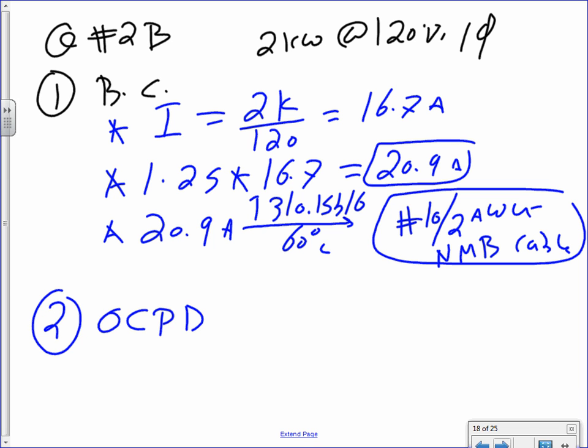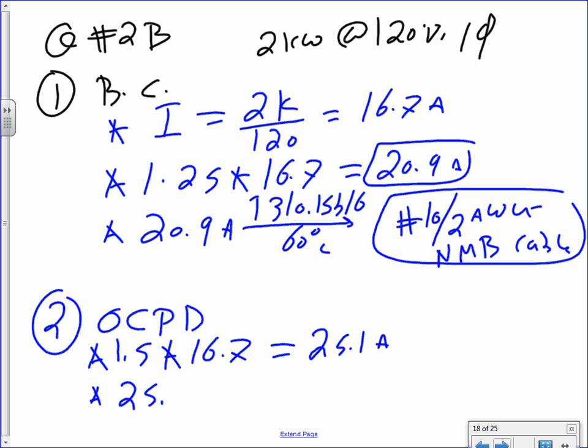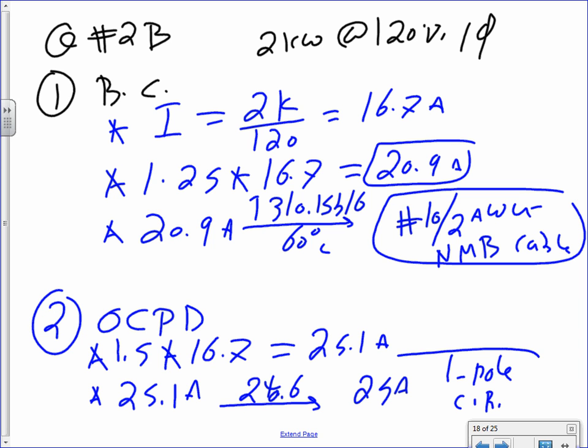Okay. For the overcurrent device, guys, the same thing. You're going to take 1.5, multiply this one by 16.7. That will get you a healthy 25.1 amps. And when you take 25.1 amps to 240.6, that will get you a 25 amp single pole circuit breaker. It's a single pole. Can you guys, does everybody know why single pole circuit breaker, not two pole circuit breaker?